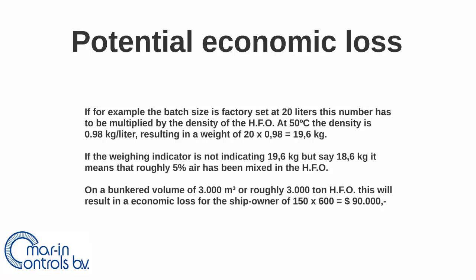If, for example, the batch size is factory set at 20 liters, this number should be multiplied by the density of heavy fuel oil. At 50 degrees Celsius, the density is most probably 0.98 kilograms per liter, resulting in a weight of 20 × 0.98 = 19.6 kilograms. If the weighing indicator is not showing 19.6 kilograms but instead 18.6 kilograms, it means that roughly 5% air has been mixed into the heavy fuel oil. On a bunkered volume of 3000 cubic meters, or roughly 3000 tonnes of heavy fuel oil, this results in an economic loss of 150 × 600 = $90,000, with 150 being 5% of 3000 tonnes and $600 the price of heavy fuel oil per tonne.